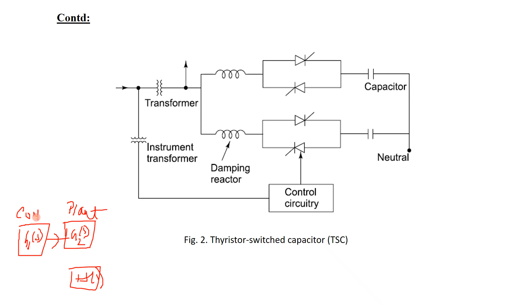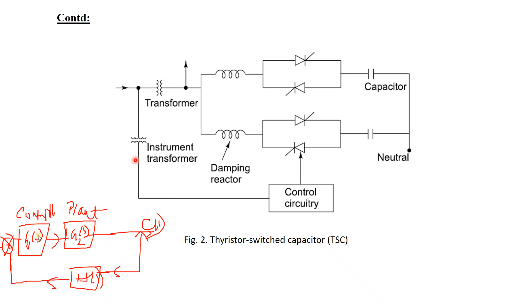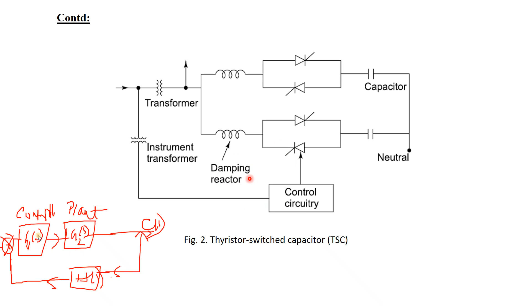Suppose this is C(s), and R(s) is the input. Input power is traveling and going inside this particular TCR, getting an output, and based on the output the feedback is sent, generally from the instrument transformer. As per the requirement of how much reactive power is needed, the thyristor triggering, rather firing, is done. So as the requirement of power changes, the firing angle also changes.